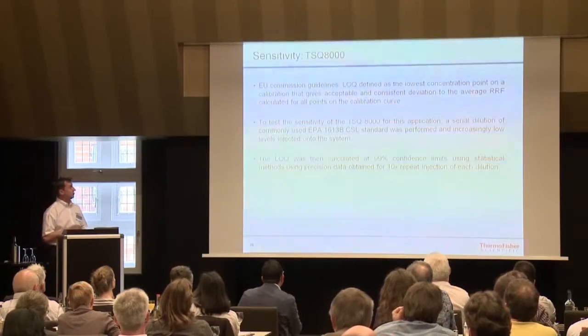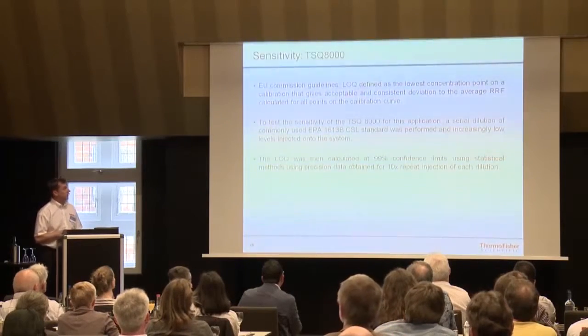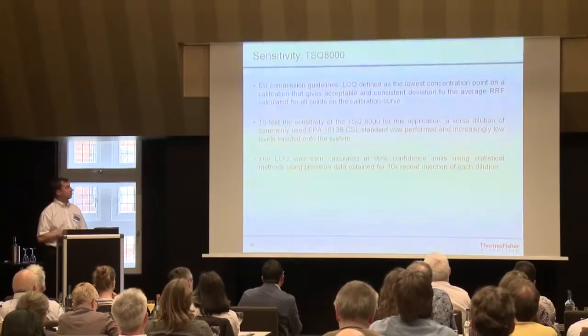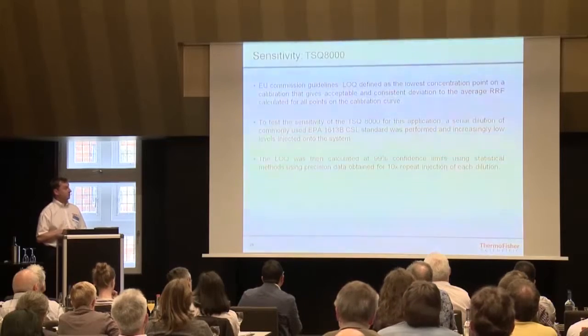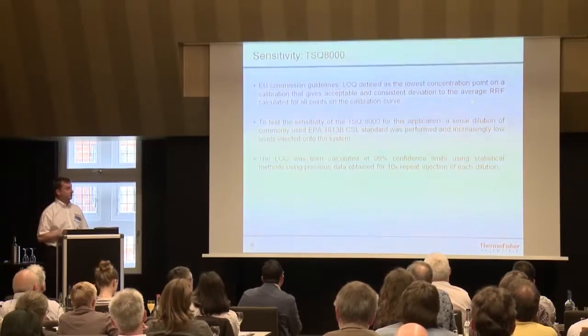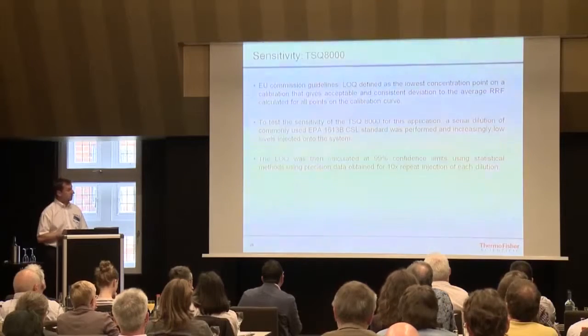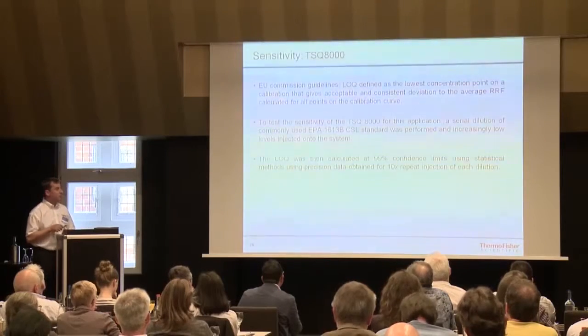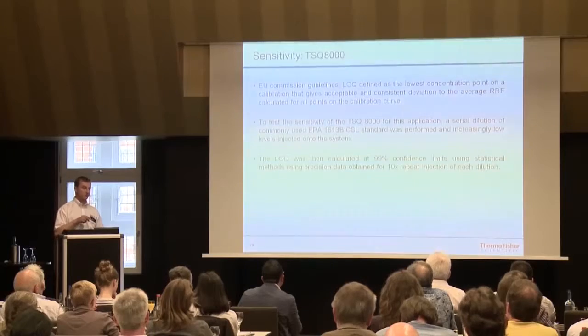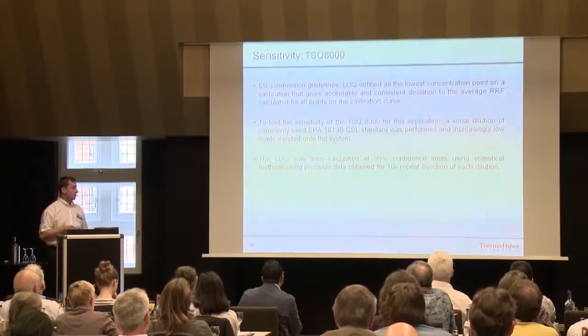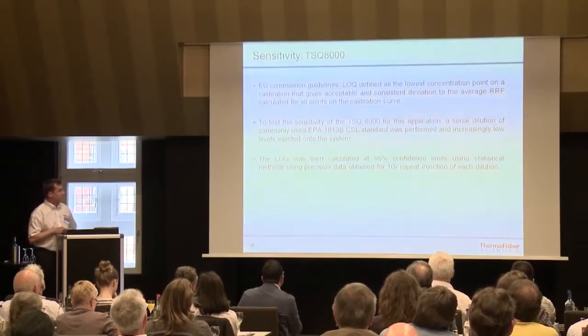Looking at the commission guidelines, the LOQ for GC-MS/MS is defined as the lowest concentration point on a calibration that gives acceptable and consistent deviation to the average response — relative response factors calculated across the calibration curve. This is again what Alexander said yesterday. We went for this empirical way of detecting the LOQs rather than the signal-to-noise or statistical approach.